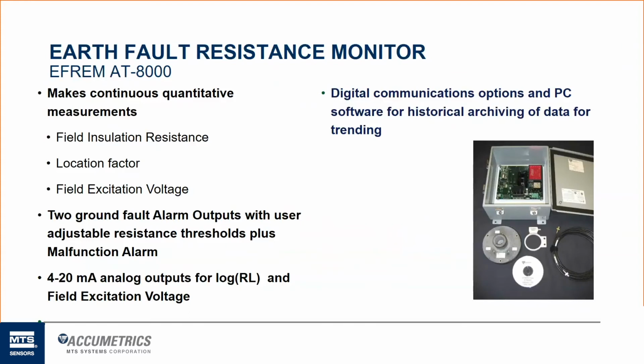We also offer digital communication options. Every system comes with its own PC software that allows you to have some historical archiving. You can trend the data through the software. It'll create a CSV file in Excel format and will allow you to trend that data. So if you, for instance, receive that warning alarm, a lot of times we'll have the customers go down to the receiver and plug right in with their laptop and start trending that information over a whole day, so that we can take a look at that data and see it kind of moving in the right direction towards a ground fault, or wrong direction if that's how they would see it.